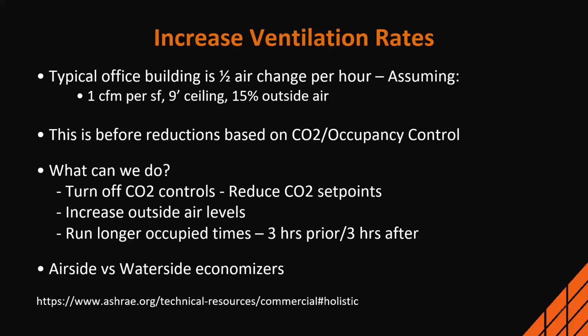So we wouldn't do that. Instead, as soon as you come in the building, it goes, okay, you're occupied, and we're going to go to 15% ventilation right out of the gate. So that helps right there. The second step is to increase our outdoor air levels. We're going to push them up as far as we can. There is no specific level you're trying to get to, just as high as you can. The recommendation is, as long as you can maintain your temperature and humidity, you want to push that number up.